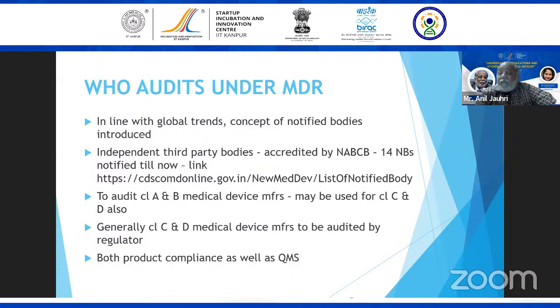They may also be used for Class C and D. May, not necessarily. Otherwise, generally, Class C and D medical device manufacturers will be audited by the regulator himself. And the audit will cover both Schedule 4 and 5, which means both product compliance and QMS compliance. So you should have implemented both the BIS standards for the product as well as the quality management system as per Schedule 5, or largely ISO 13485.